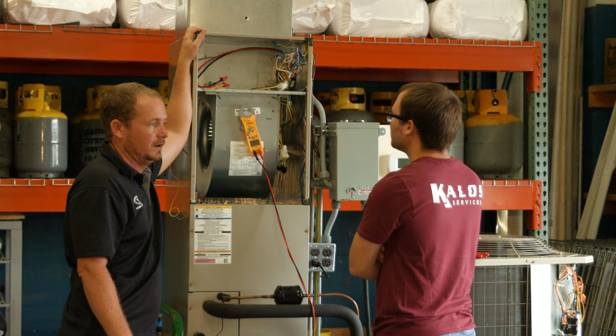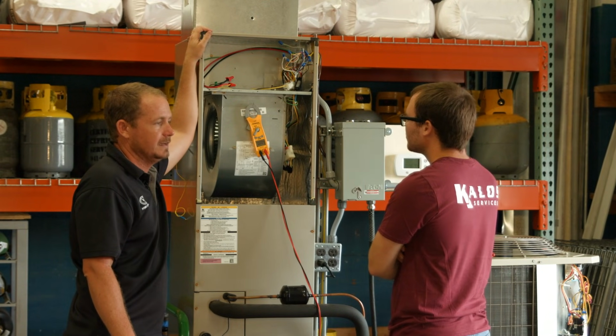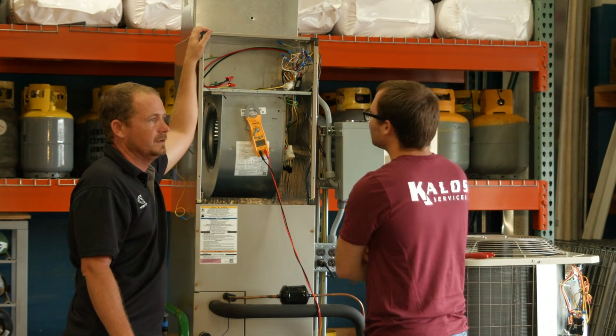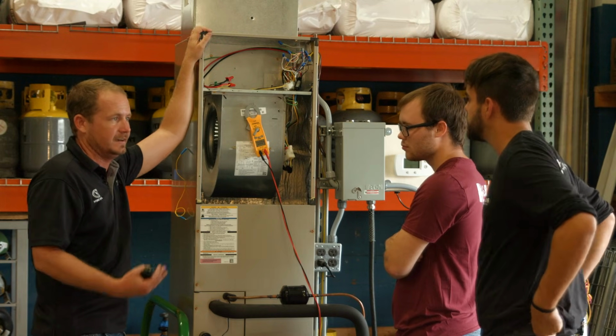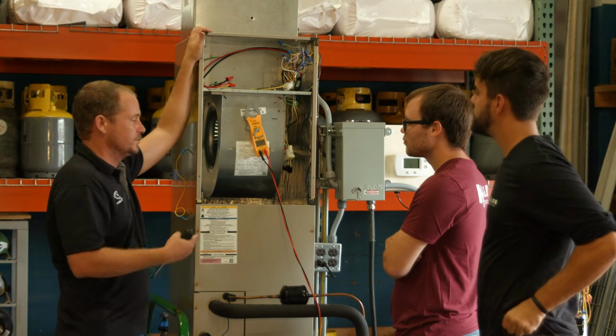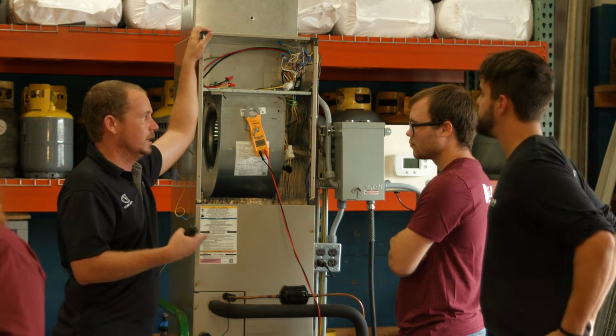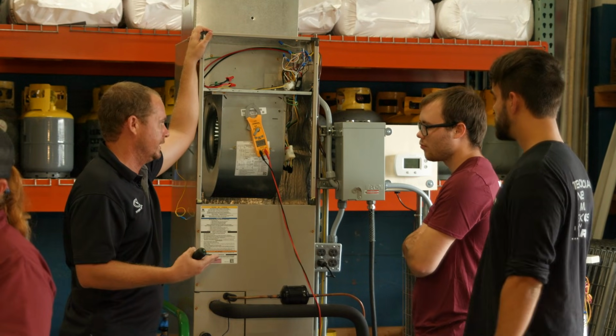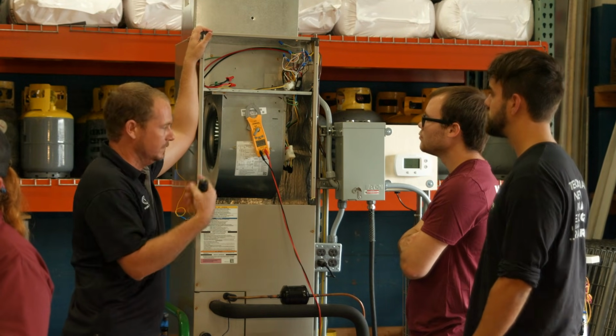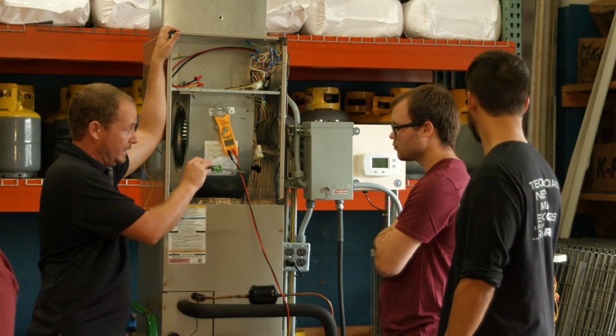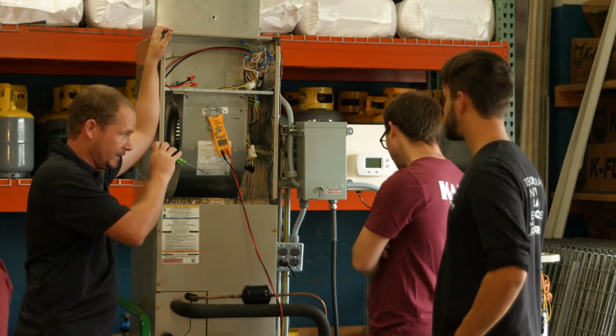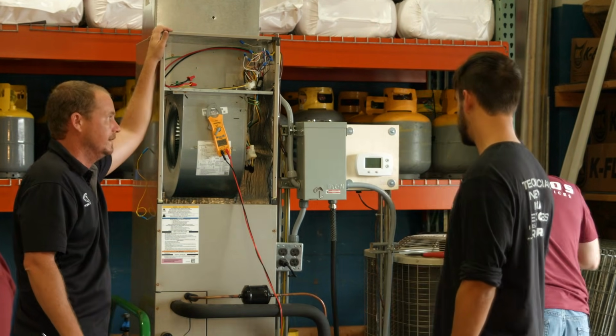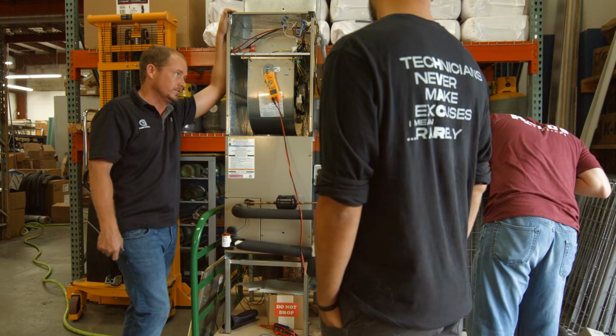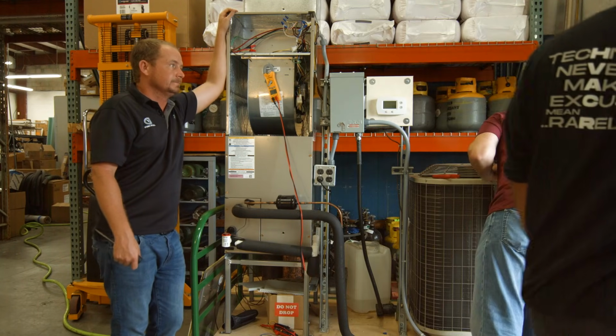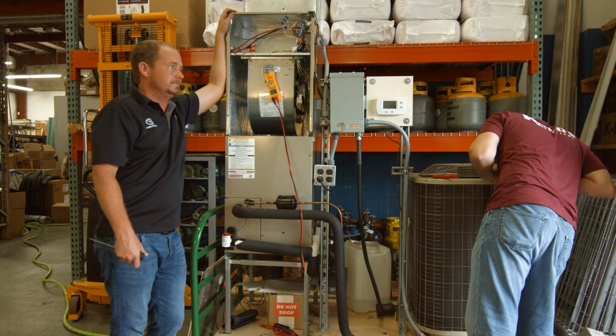All right, Eli, come on over here. He needs some help. We've got it. He's in his visual inspection phase here. His system's running in heat mode. So we talked through some things that you would definitely want to check, but where do we want to look? So definitely, if you haven't looked at the reversing valve yet, just take a look at it and make sure, is that coil attached to the reversing valve? It's running in heat mode.